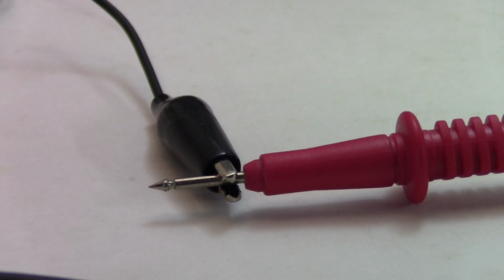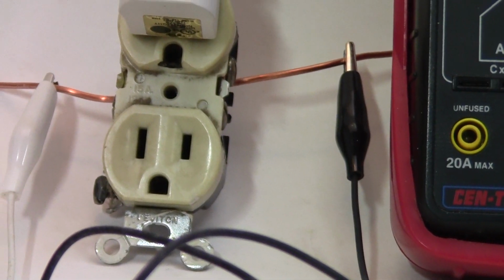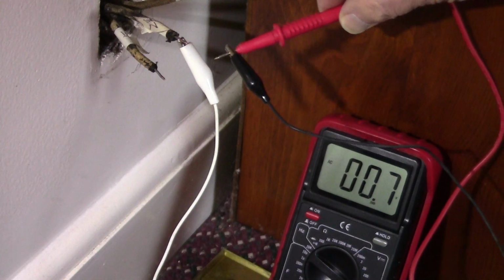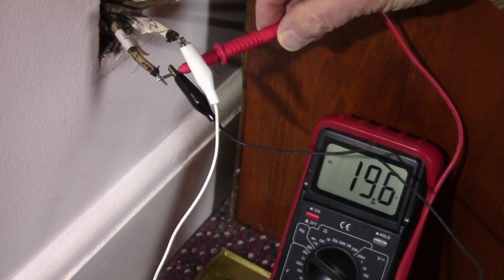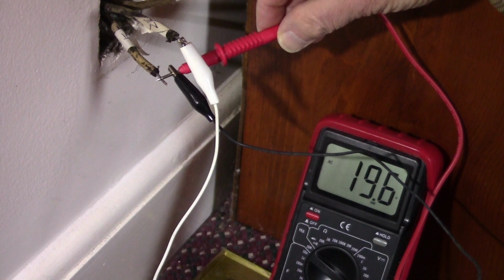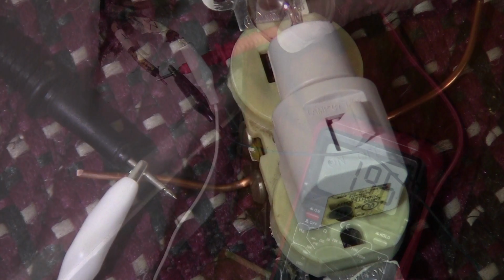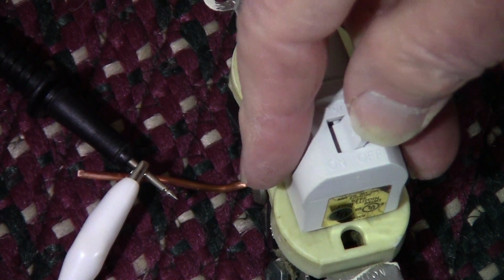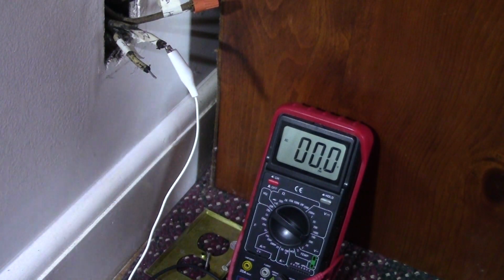Connect a black clip lead to the DVM red probe and also to hot on the outlet. With the nightlight switched off, make the phantom voltage measurement by touching the red probe and attached black clip lead to the hot wire on the circuit you are testing. You will see the phantom voltage on the DVM. Now switch the nightlight on and repeat. You will see the phantom voltage reduced to 0 or something very small.